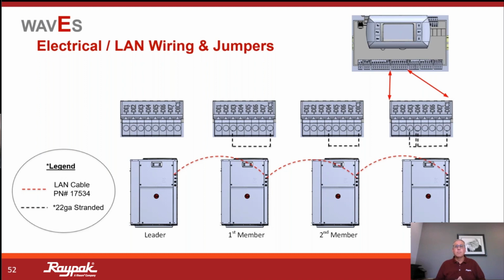That's fine. Yeah, and so you're not basically using the control screen to set the number of the unit. You're using a jumper. Well, Peter, another good observation. You're actually going to do both, but we're going to talk about the programming and commissioning of these, as well as the number of compressors and which one is which. So more to follow in Level 3 when we do startup and commissioning and programming.